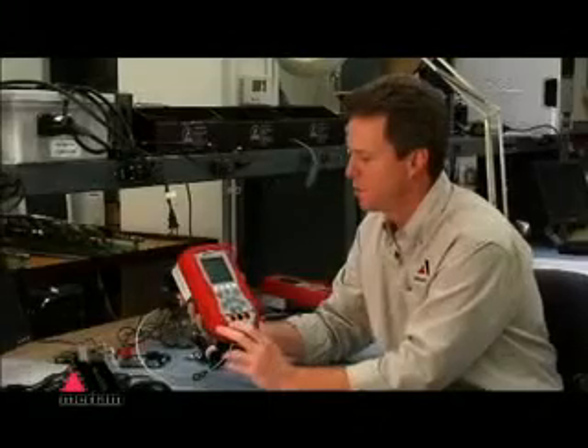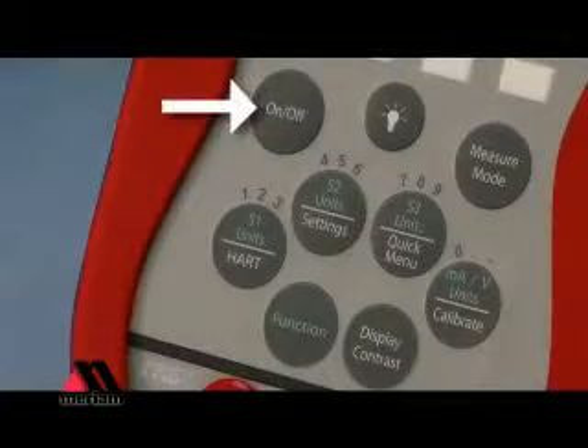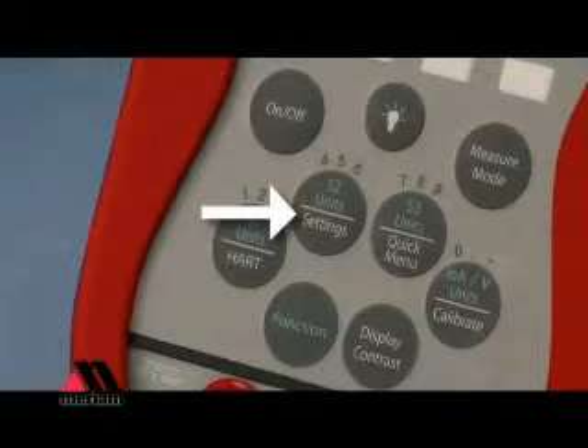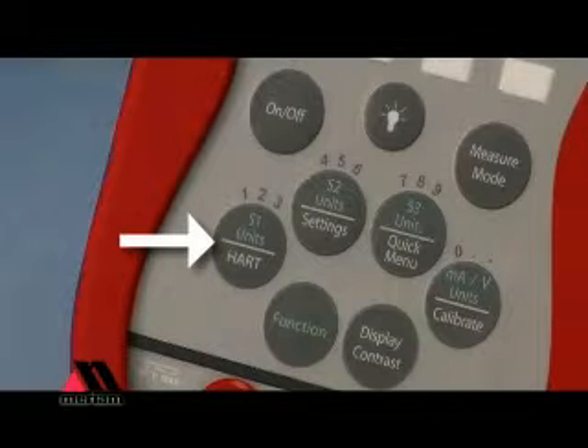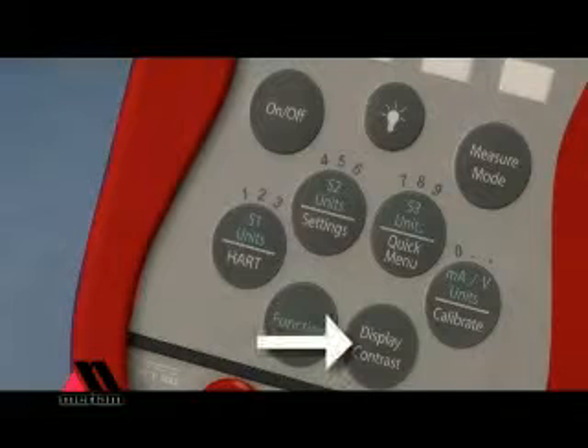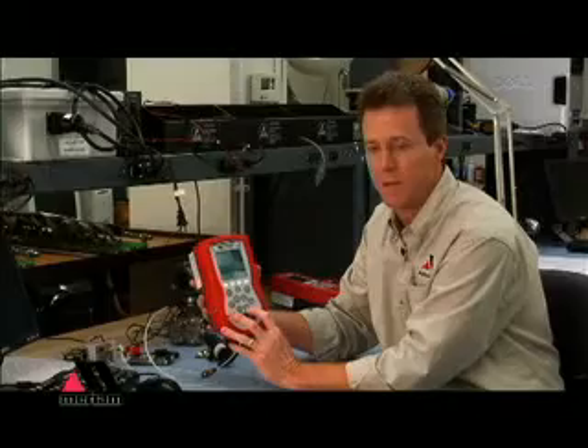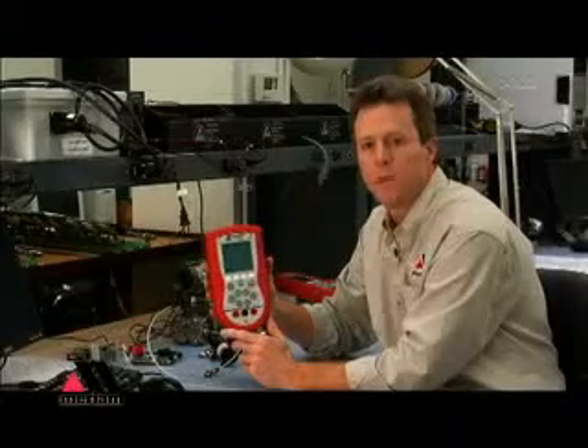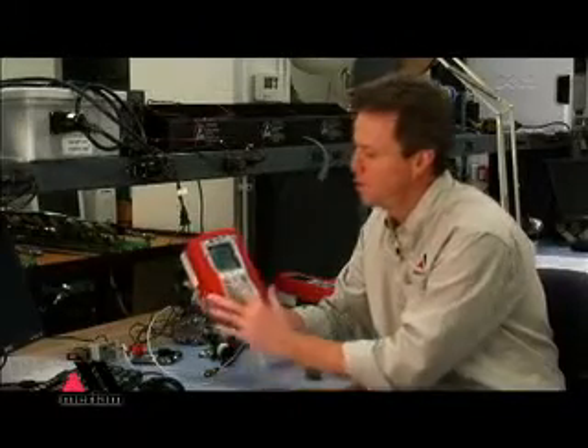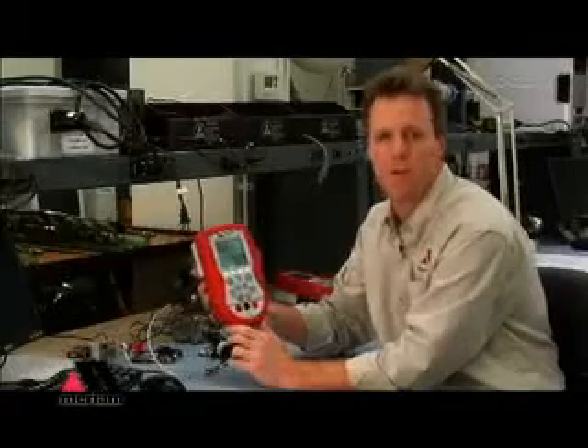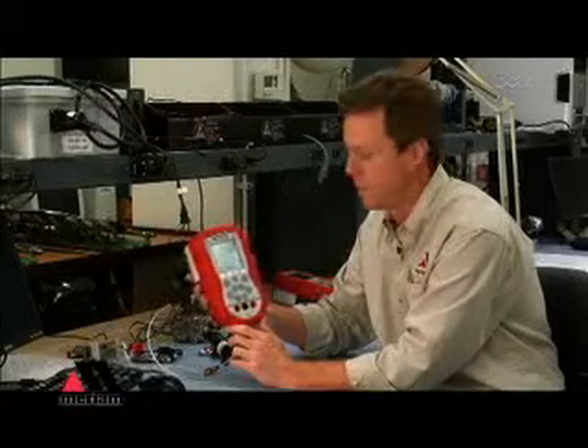The keypad allows you to turn the unit on, turn the backlight function on, adjust settings of the instrument, access the HART communication functions, access quick menus and calibration features. There's also a contrast adjust key that allows you to adjust that contrast from any point in your use of the MFT. The display will show you up to 4 measurements at any one time, and it also tells you the definitions of the white soft keys that are located immediately beneath the display. Those soft keys change in their functionality depending on where you are in the use of the MFT.